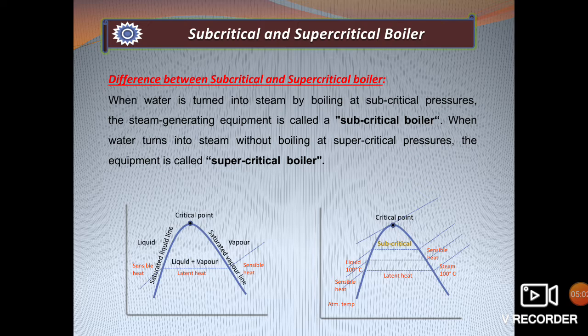In a supercritical boiler, the operating pressure is always more than the critical point. That means there is no latent heat exchange. The saturated liquid is directly converted into saturated vapor, and there is no need for a drum since there is no latent heat exchange and no mixture of water and vapor present.